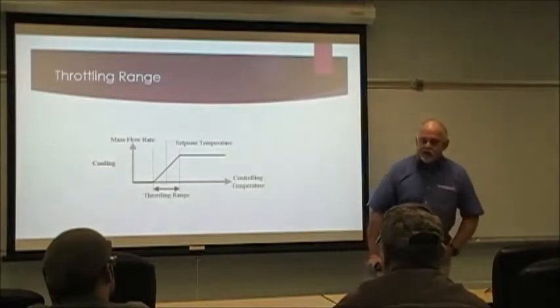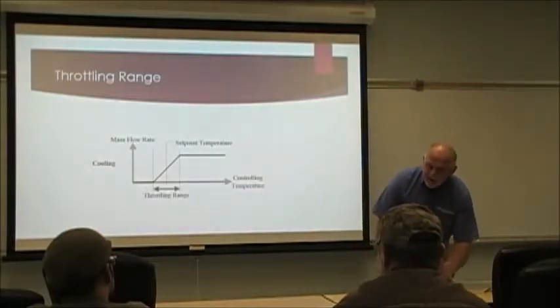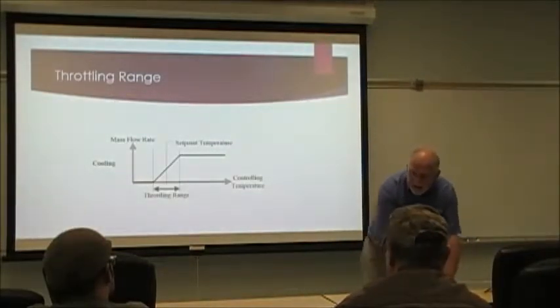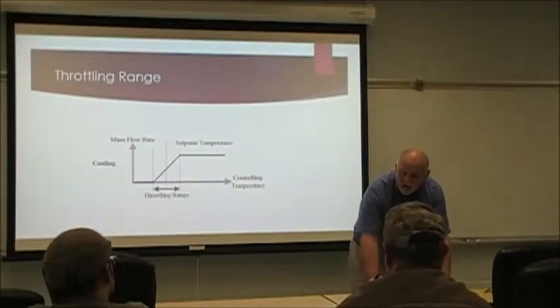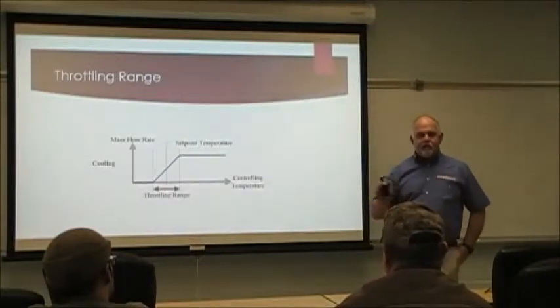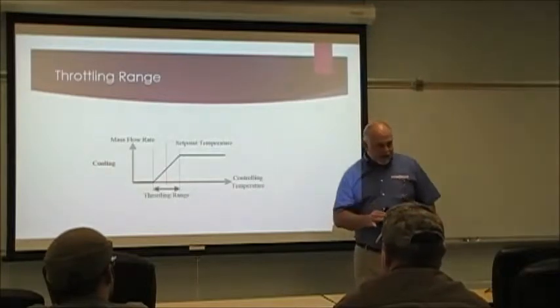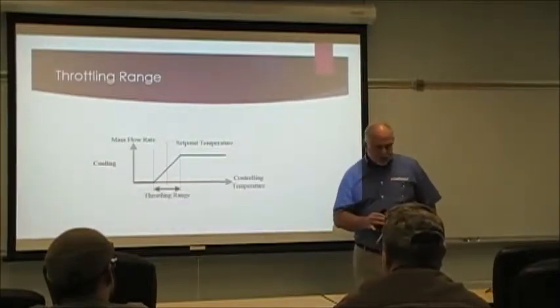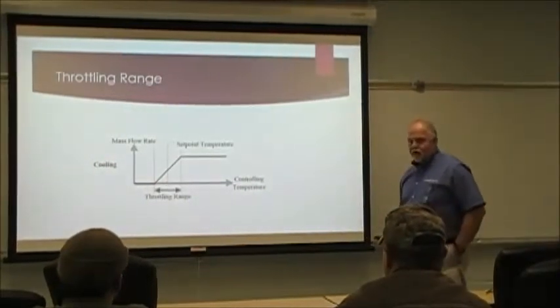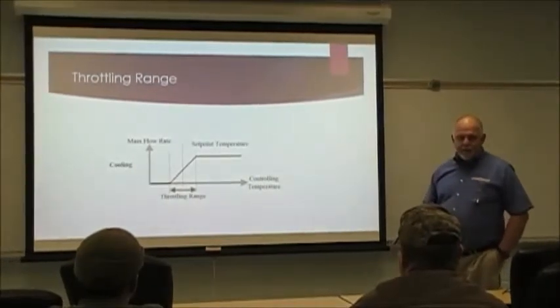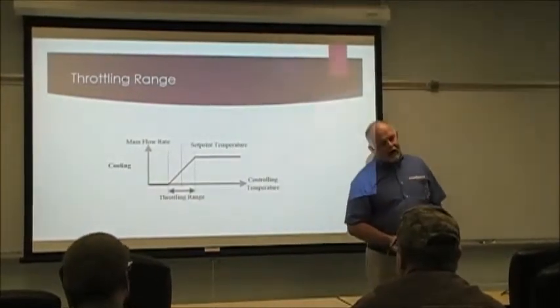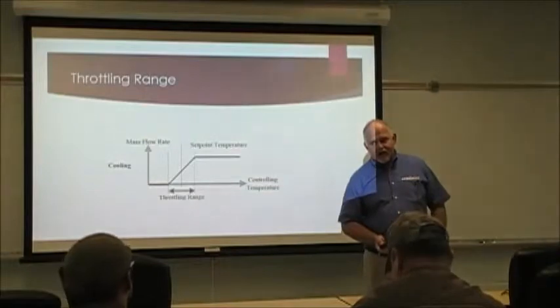Now, if your throttling range was 10 degrees, let's say it started at 72, and it had a throttling range of 10 degrees. At 82, that cooling valve would be fully open. You understand that concept? Okay. You sure you understand the concept? Because I'm prone to lousing stuff up occasionally, not saying it just right.